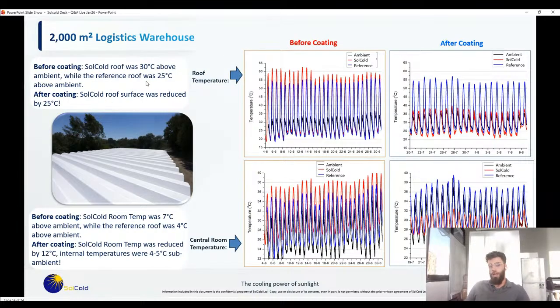This is a large logistics warehouse, 2,000 square meters, that we did here in Israel. Before the coating, the SolCold roof is shown by the red lines in the graph, and our reference building - a building the same size in the same area next door - was actually 2 degrees colder due to a bit more airflow, even reaching 5 degrees colder. We decided to coat the hotter warehouse. After coating, we reduced the roof surface temperature by 25 degrees, down to a nice cold 35 to 40 degrees Celsius. This was in the middle of July.